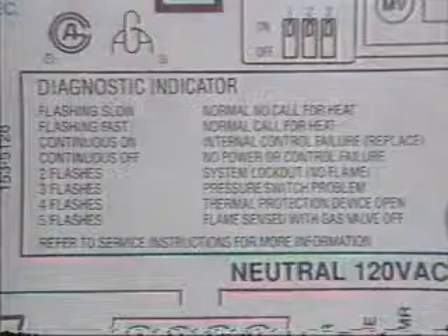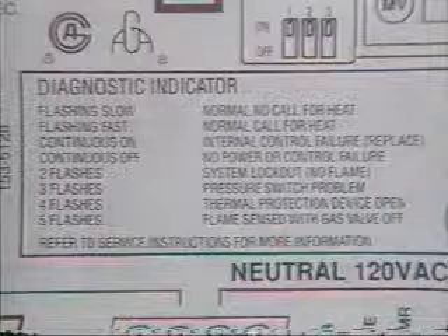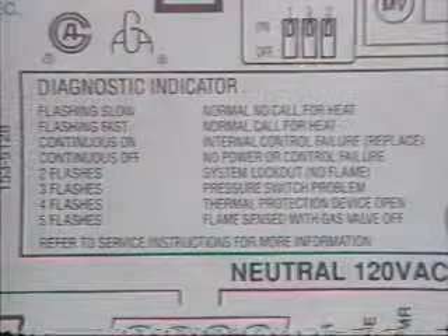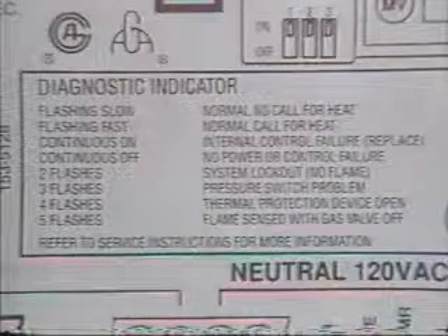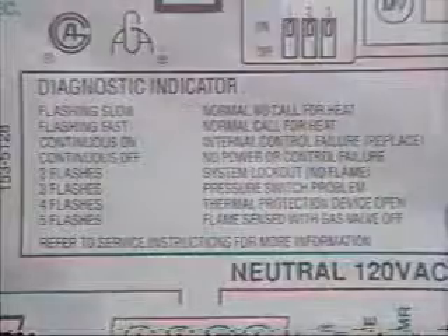A flashing light with pauses indicates a problem is most likely in the external components or wiring. The number of flashes between pauses is used to aid in diagnostics. The LED flash pattern helps indicate the probable location by the number of flashes between each pause.